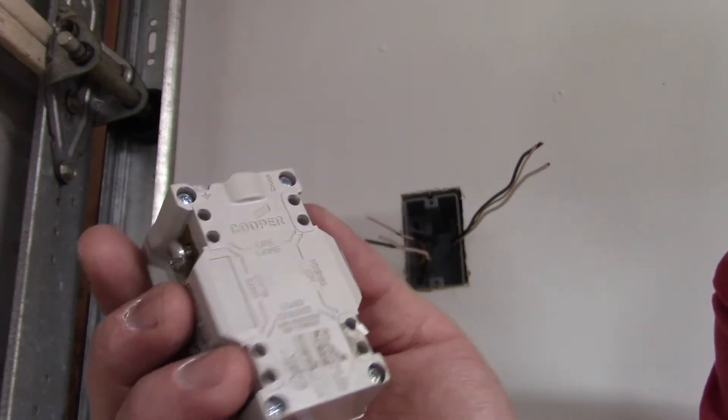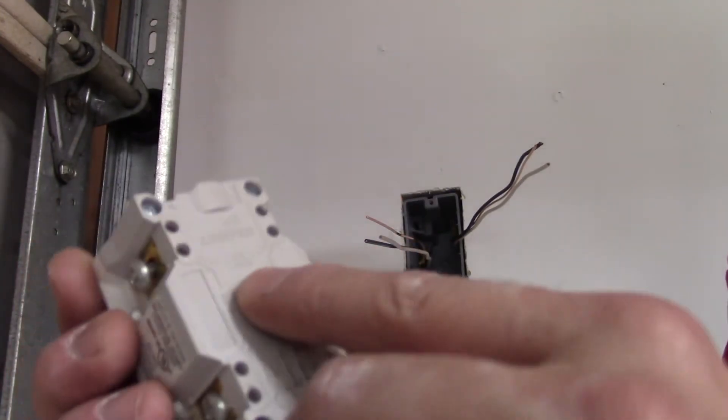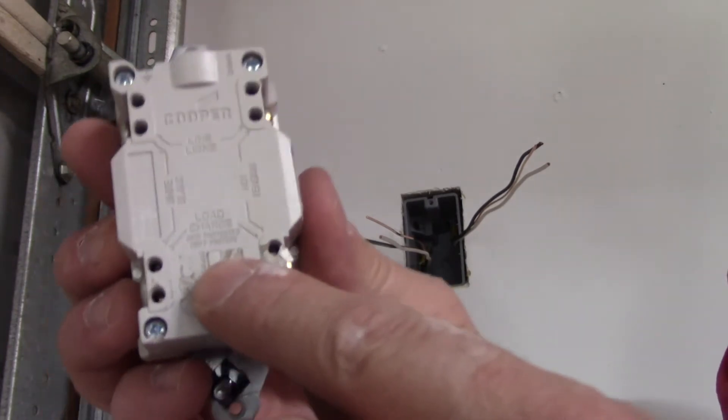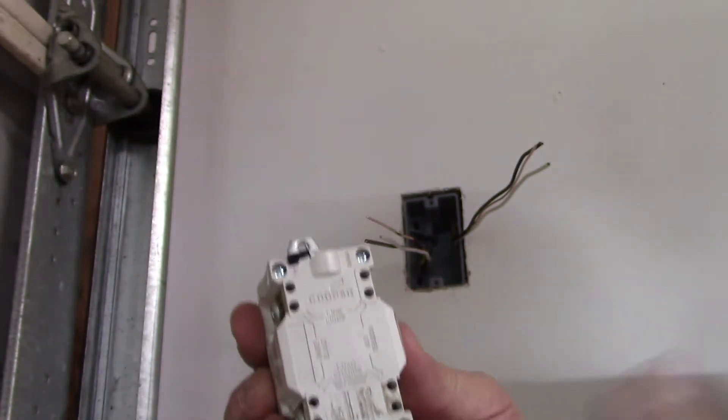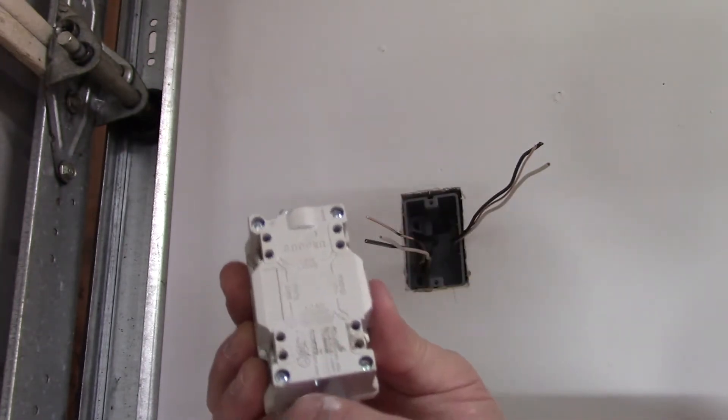On your GFCI outlet on the back, one side or one end of it is going to be marked line. This is the set of terminals that gets the power. And the other end of it is going to be marked load. And that is the circuit that continues on from this GFCI that will be protected by this outlet.